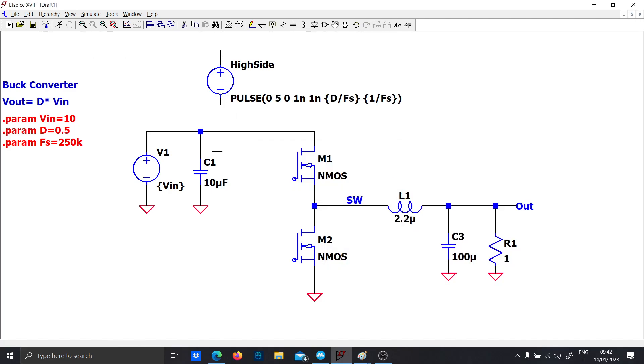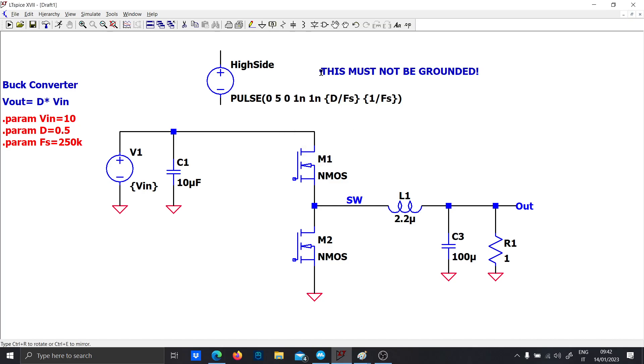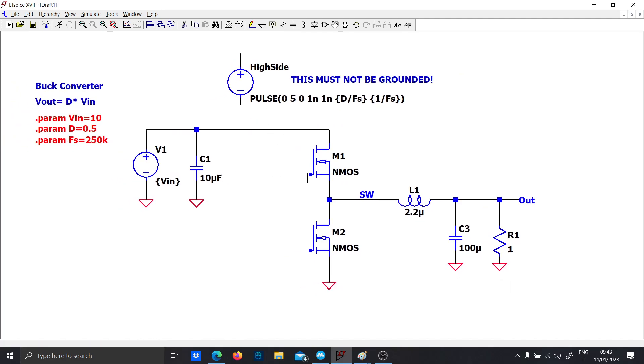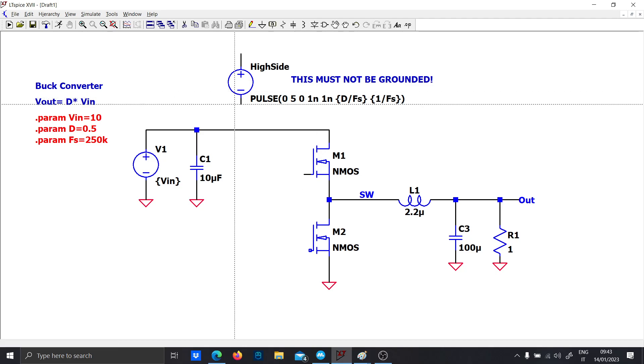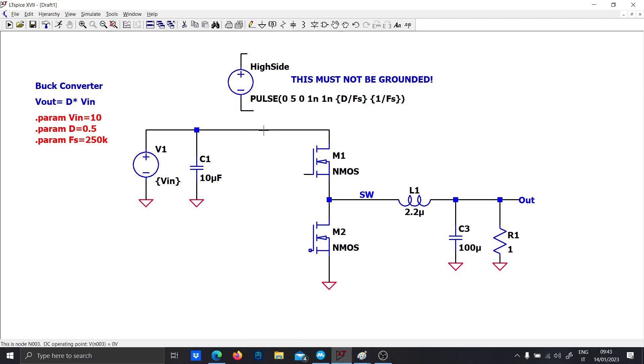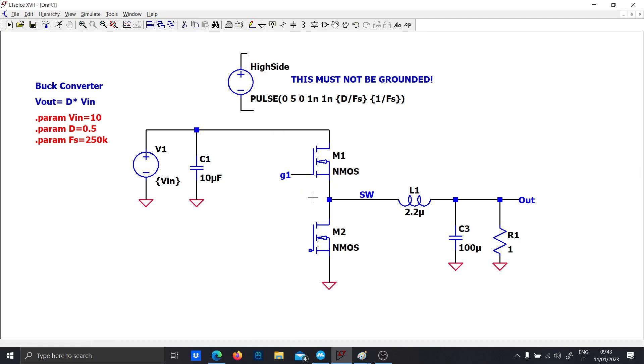Be extremely careful: the high-side generator must not be grounded. The high-side switch does not have a ground reference. In order to turn on the switch you have to supply a gate-to-source voltage greater than 5 volts, so you have to connect the high-side driver between the gate (let's call it Gate 1) and the switching node.